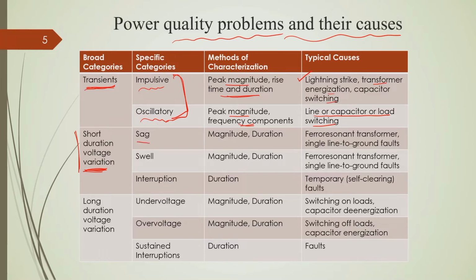Voltage sag is a sudden short duration voltage dip, which is characterized by its magnitude and duration. The possible causes for this kind of power quality problem are ferroresonant transformers and single line to ground faults, which are very frequent types of faults that distribution networks encounter.